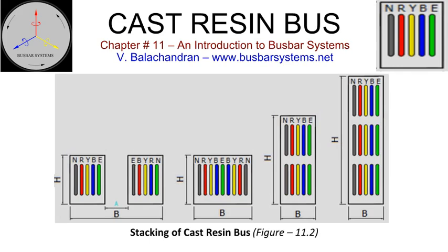For higher current ratings, it is a norm to provide up to 3 parallel paths for a single connection. There are several alternatives to achieve this objective. The parallel conductors can be embedded in a common casting, stacked either horizontally or vertically, or cast individually and run alongside. Note the configuration of the conductor for ease of paralleling at the terminating end when stacked horizontally.